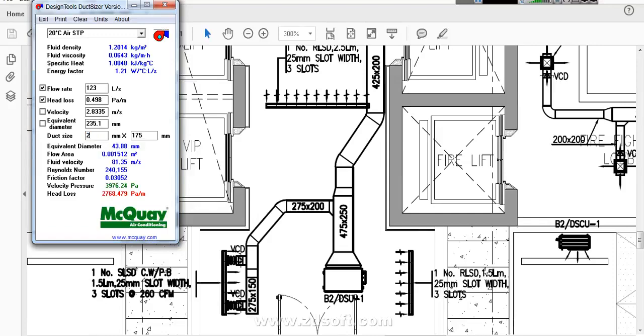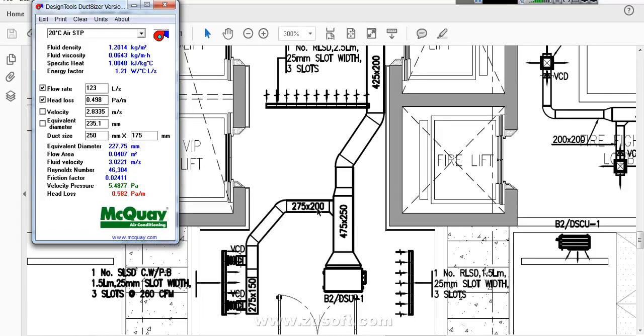If I am putting 250, it equals 250 into 175. That also because 25mm difference is there. Here it is 250, here 275, here 175, here 200. That means there is internal lining. And when you come down to this portion, last portion, they again reduce the size 275 by 150, because there is a branch already taken, that's why this portion they have made it down.